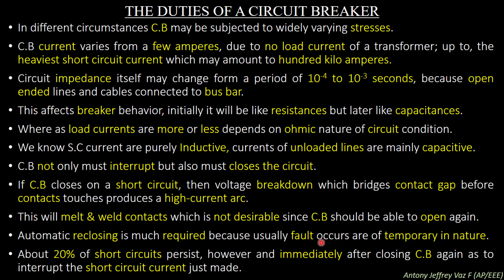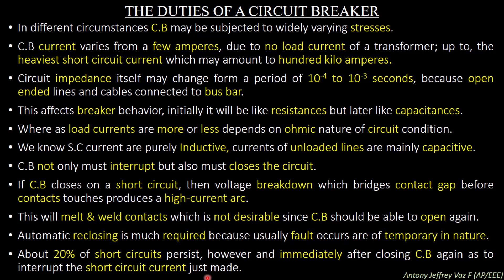This is a very severe duty, especially if there are extremely high currents requiring heavy contacts to be accelerated and decelerated. With automatic reclosing, the contacts in the circuit breaker should be accelerated or decelerated to be turned on or turned off. During the turn on process, the contacts should come closer and touch each other. In a turn off process, the two contacts should be separated. This acceleration and deceleration depends on the fault location and the type of fault.